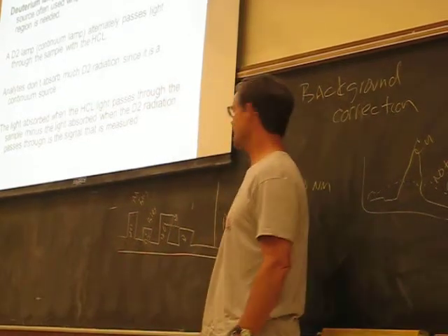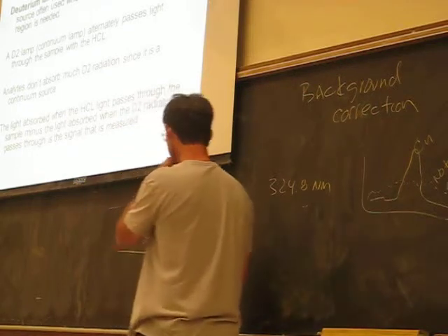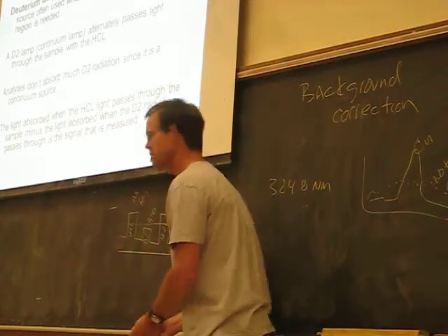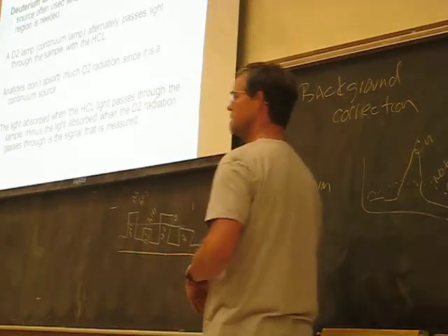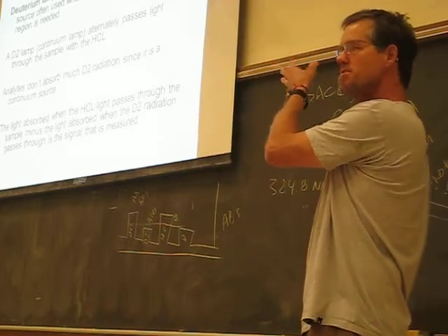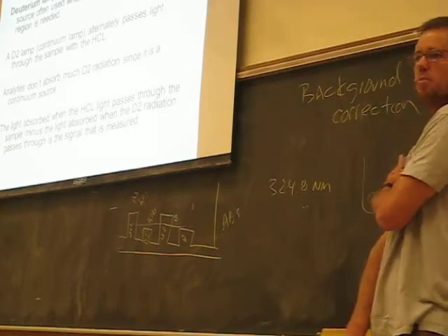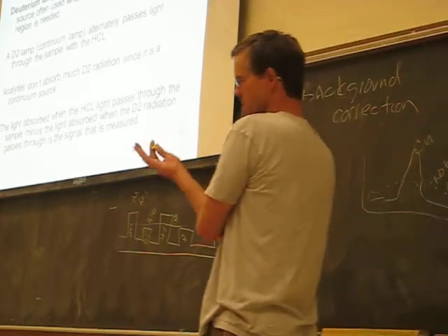That's how it calculates, generating the result by difference. You get the idea of what I'm trying to draw. That's a relatively inexpensive form of background correction used in flame atomic absorption spectrometers.